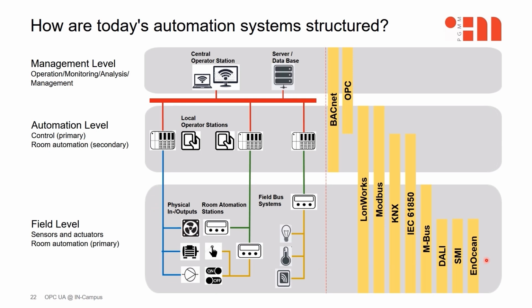The following technologies can be mentioned in particular as communication systems for the field bus level. EnOcean, for communication with radio sensors and radio actuators. SMI for communication with blinds. DALI for communication with lighting systems. M-Bus for communication with meters. IEC 61850 for communication with electrical equipment. KNX and LonWorks for communication with actuators, sensors, and application-specific devices and controllers of the field level, and finally Modbus for communication with selected devices and systems.